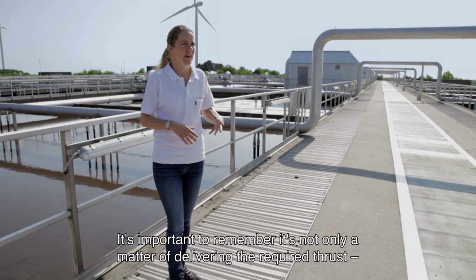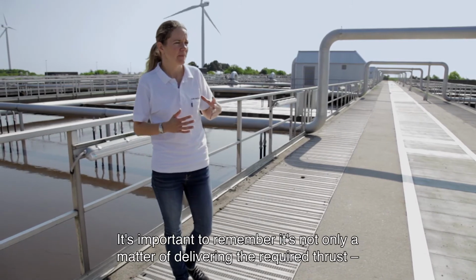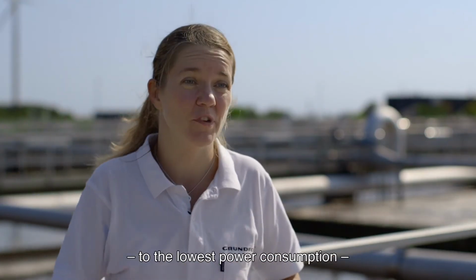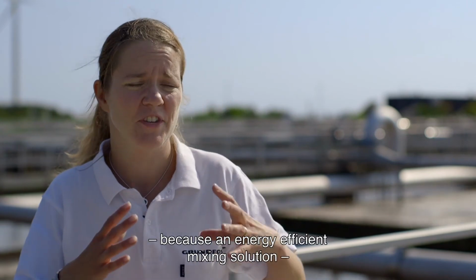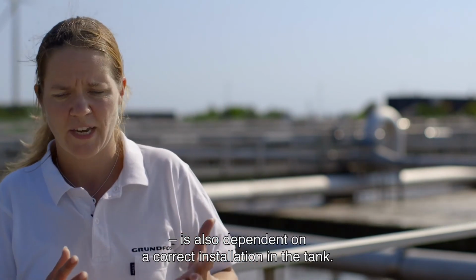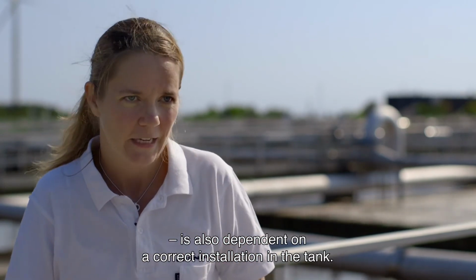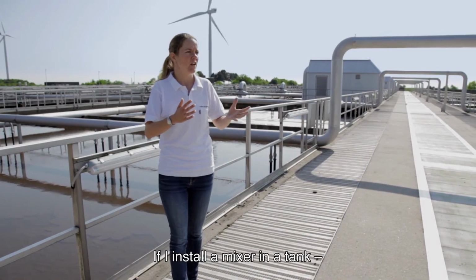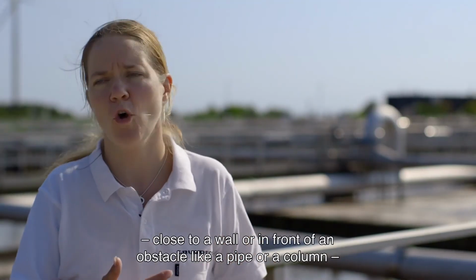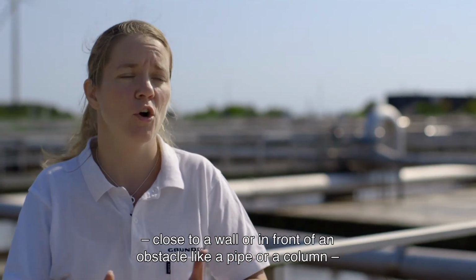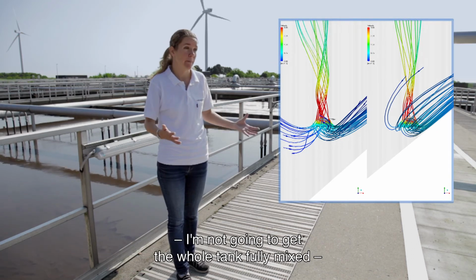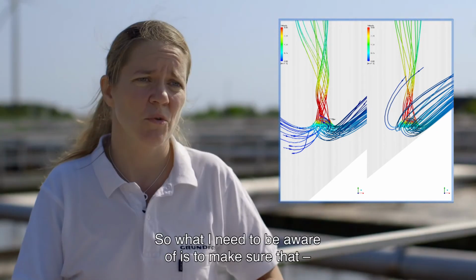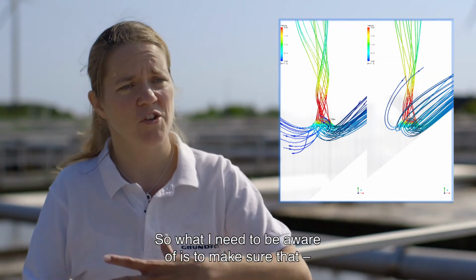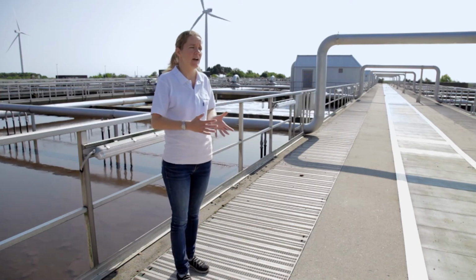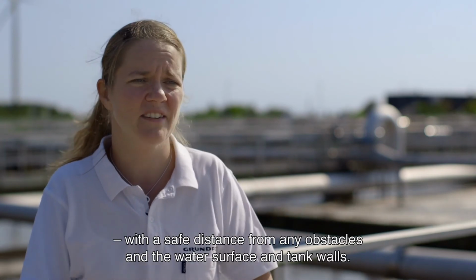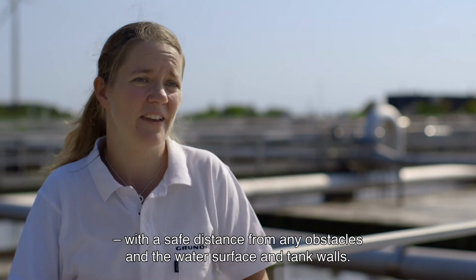It's important to remember that it's not only a matter of delivering the required thrust to the lowest power consumption, because an energy-efficient mixing solution also is dependent on a correct installation in the tank. If I install a mixer in a tank close to a wall or just in front of an obstacle like a pipe or a column, I'm not going to get the whole tank fully mixed, even if the potential is there. So what I need to be aware of is to make sure that the installation of the mixer should be with a safe distance from any obstacles and the water surface and tank walls.